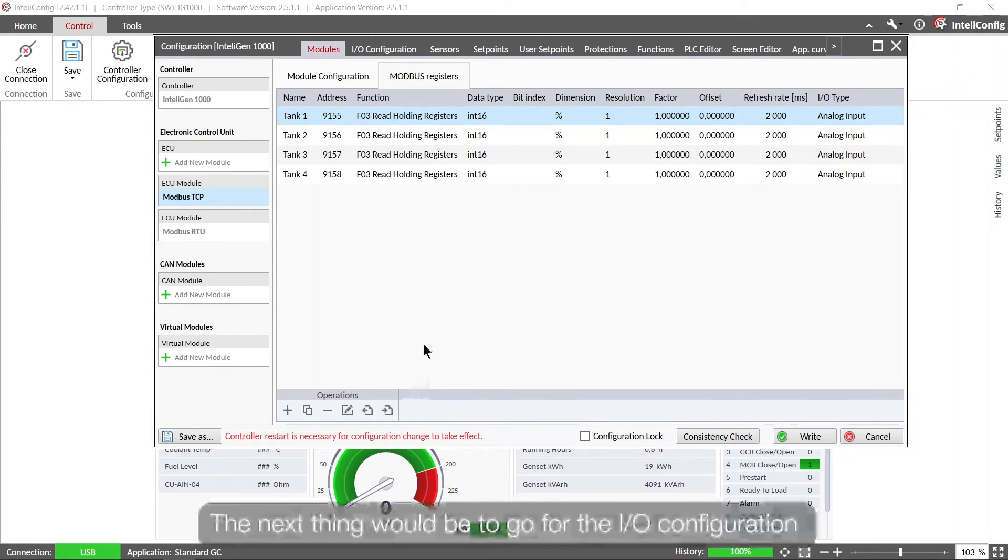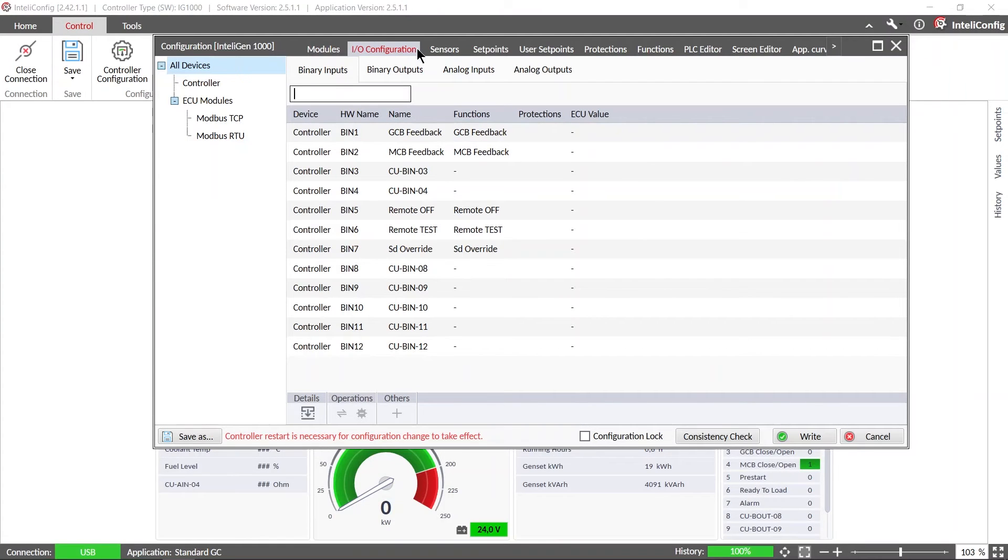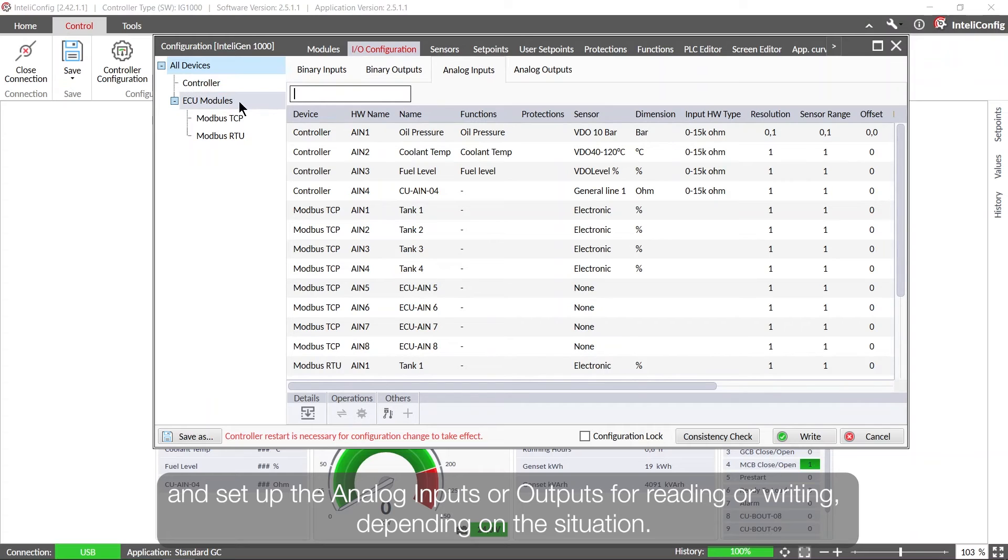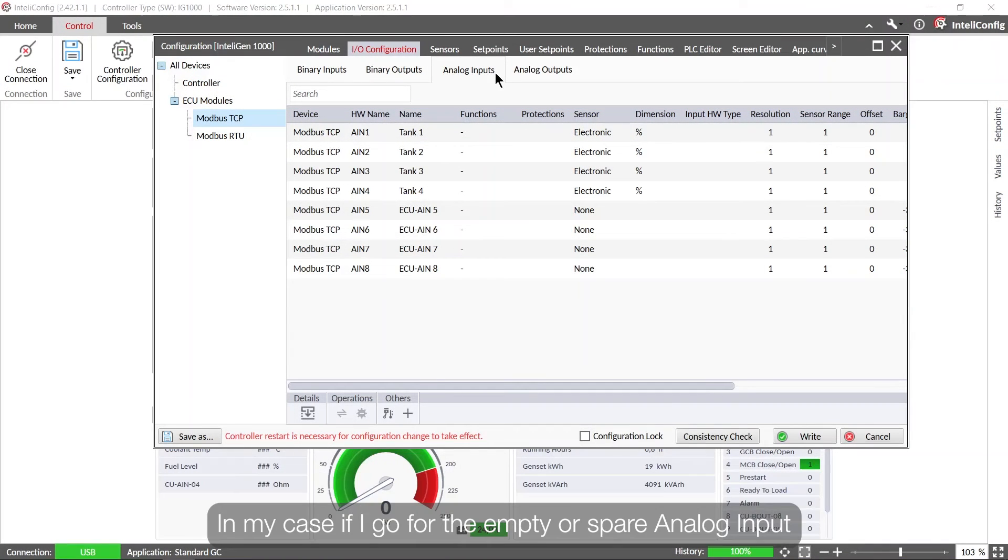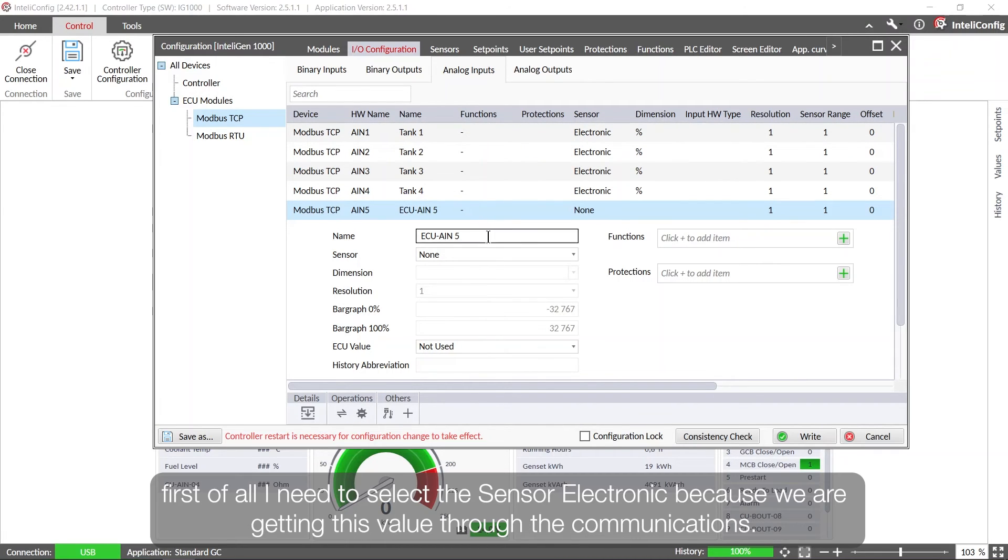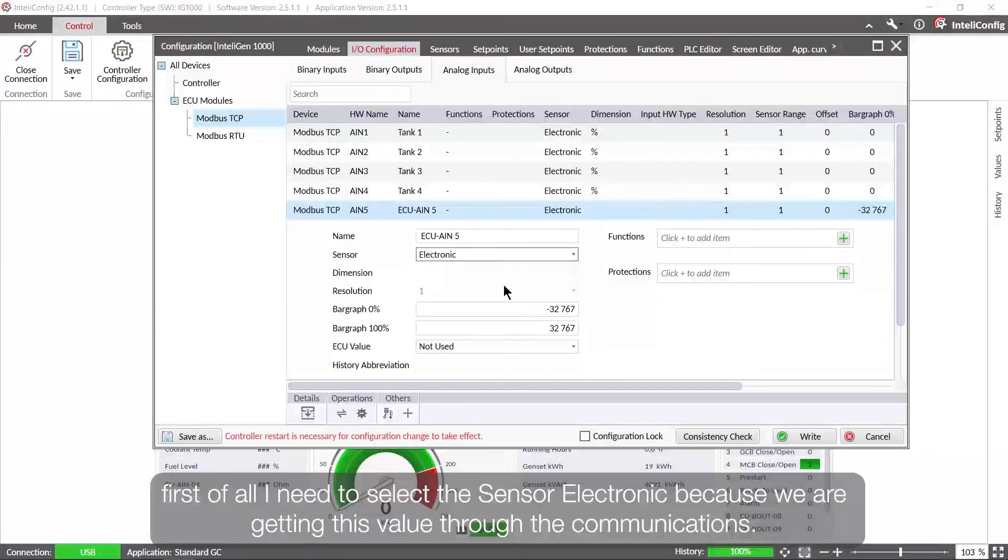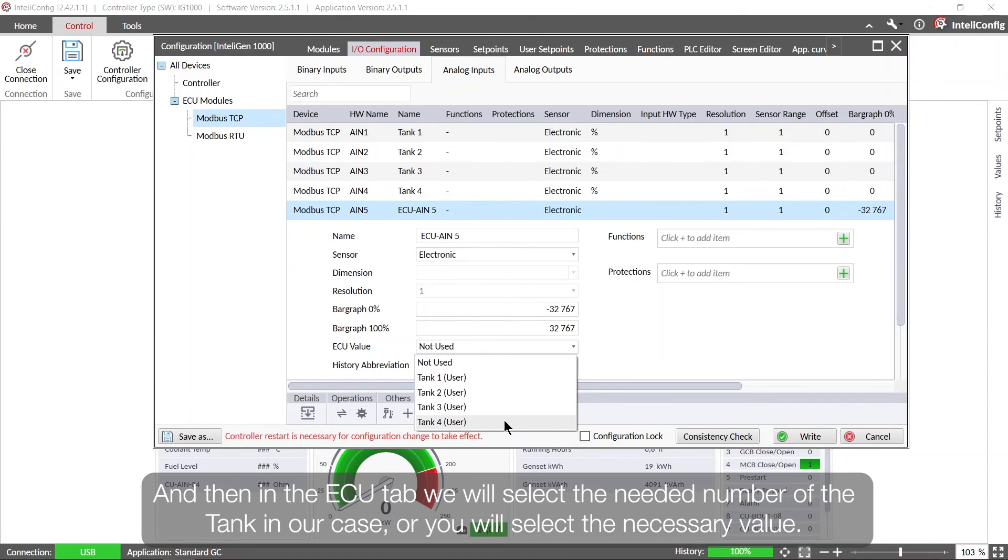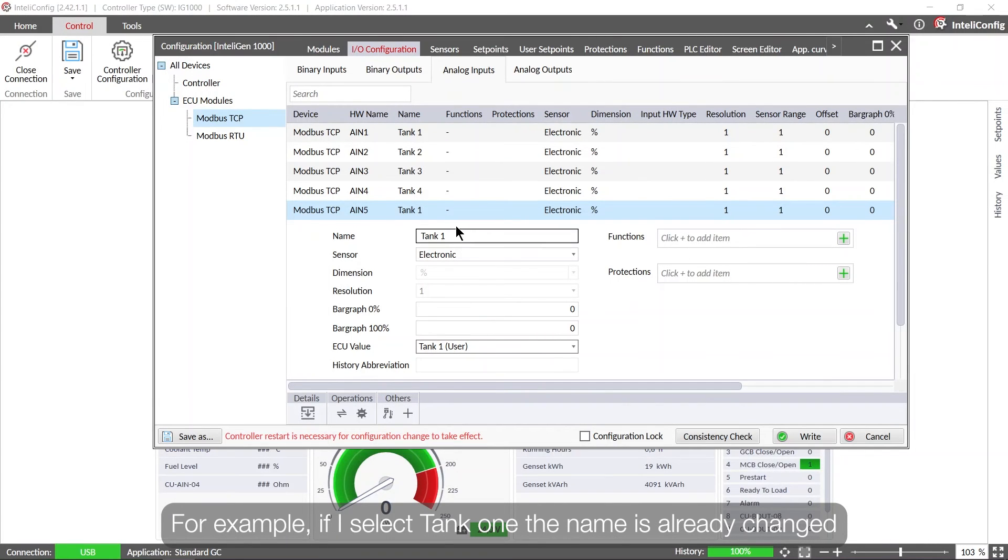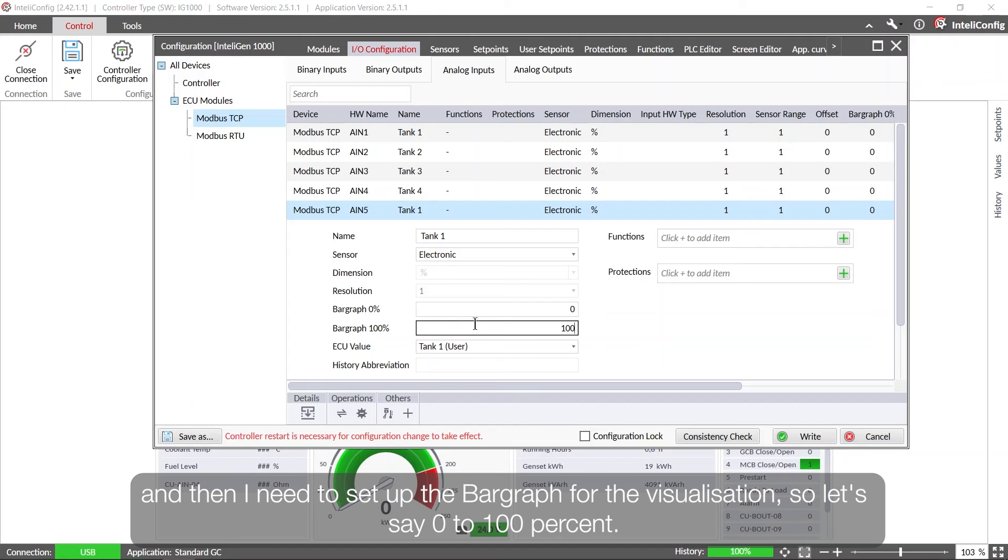The next thing would be to go for the IO configuration and set up the analog inputs or outputs for reading or writing depending on the situation. So in my case if I go for the empty or spare analog input, first of all I need to select the sensor electronic because we're getting this value through the communications, and then in the ECU tab we will select the needed number of the tank in our case, or you will select the necessary value. So for example if I select tank 1, the name is already changed and then I need to set up the bar graph for the visualization. So let's say 0 to 100%.